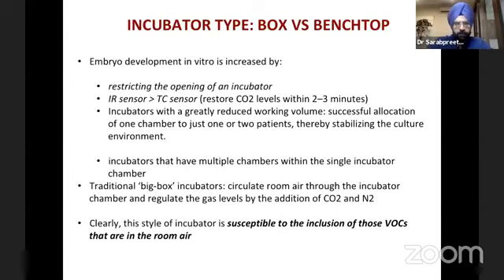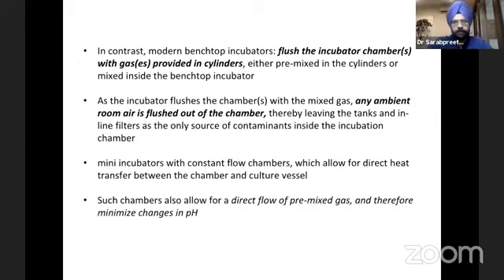Clearly, this type of incubator is susceptible to the inclusion of those VOCs that are in the room air, because a lot of ambient air also comes in. That is why it is so important to control the lab environment. In contrast, modern benchtop incubators flush the incubator chambers with gases provided in cylinders, either pre-mixed or mixed inside the benchtop, and any ambient room air is flushed out of the incubator, preventing the VOCs from impacting the embryonic development. These incubators also allow for a direct flow of pre-mixed gases and minimal changes in pH, and faster recovery also.